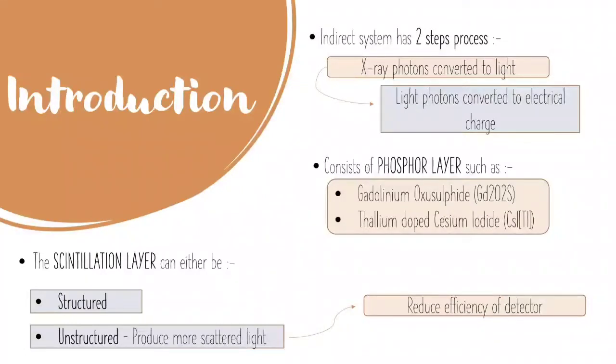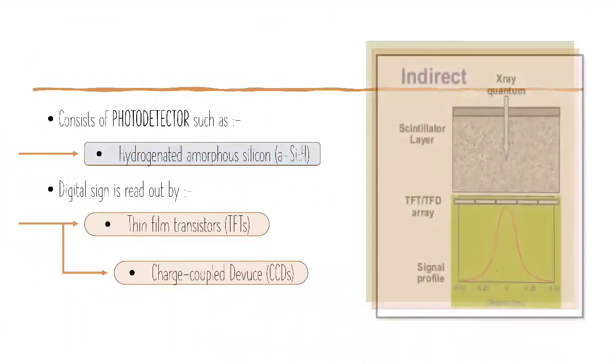This flat panel system consists of a phosphor layer, such as gadolinium oxosulfide and thallium-doped cesium iodide. The scintillation layer can either be structured or unstructured, but unstructured will produce more scattered light, hence reducing the efficiency of detection. It also consists of photodetectors such as hydrogenated amorphous silicon.